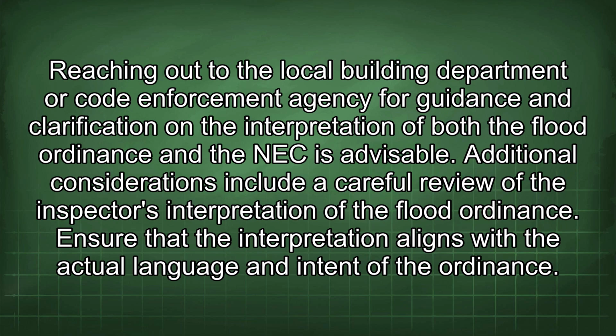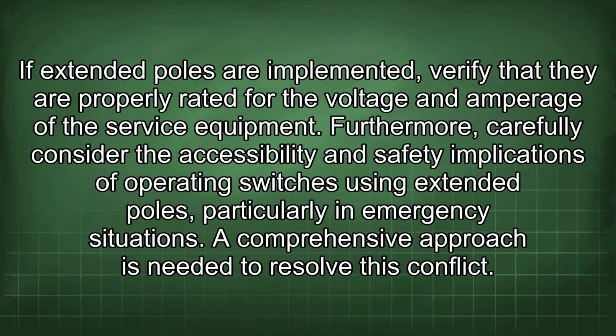Additional considerations include a careful review of the inspector's interpretation of the flood ordinance. Ensure that the interpretation aligns with the actual language and intent of the ordinance. If extended poles are implemented, verify that they are properly rated for the voltage and amperage of the service equipment. Furthermore, carefully consider the accessibility and safety implications of operating switches using extended poles, particularly in emergency situations.